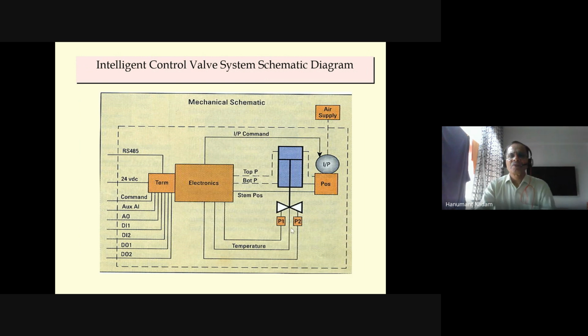So this is a mechanical schematic. You can see here, electronics is here, and from this electronics so many outputs and inputs are generated. Interfaces are also available with the DCS, either through these sync commands or HART signal or RS485 Modbus. So just see here, this is your valve.